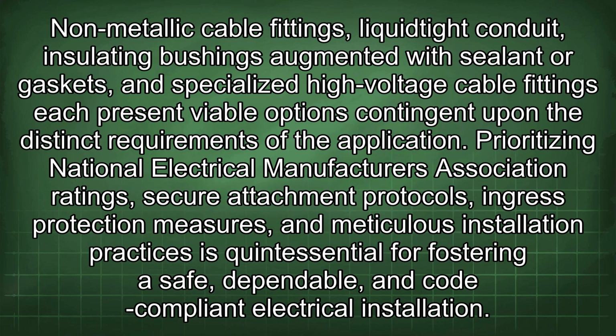Non-metallic cable fittings, liquidtight conduit, insulating bushings augmented with sealant or gaskets, and specialized high-voltage cable fittings each present viable options contingent upon the distinct requirements of the application. Prioritizing National Electrical Manufacturers Association ratings, secure attachment protocols, ingress protection measures, and meticulous installation practices is quintessential for fostering a safe, dependable, and code-compliant electrical installation.